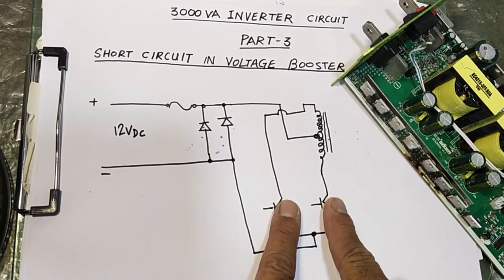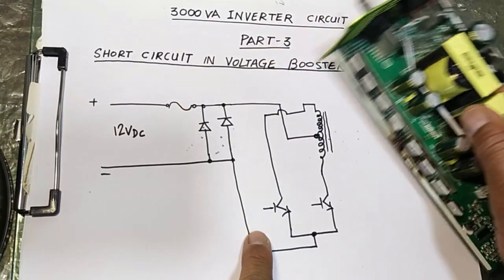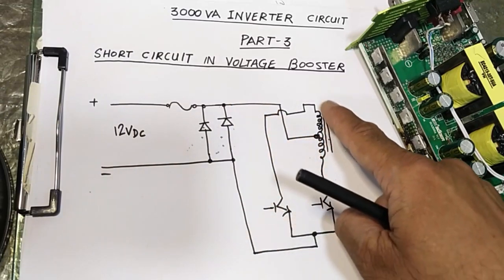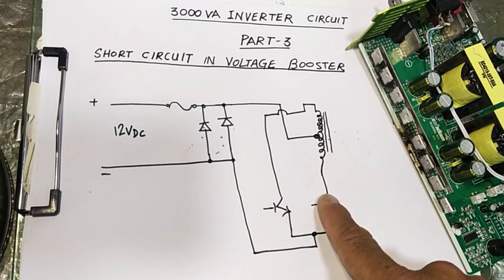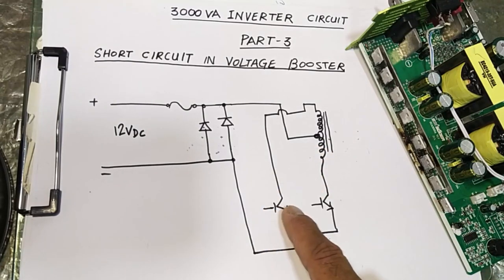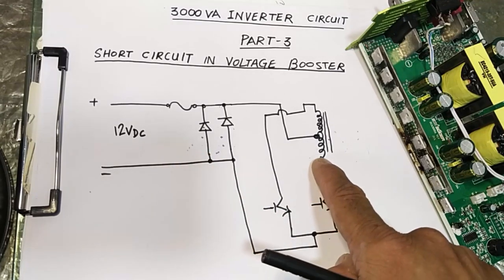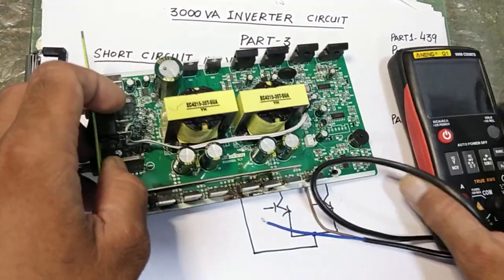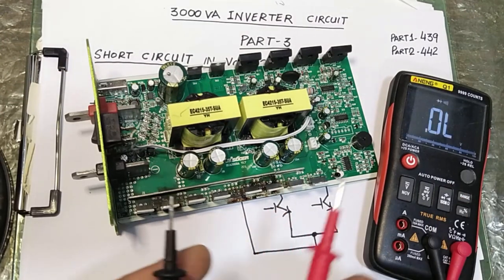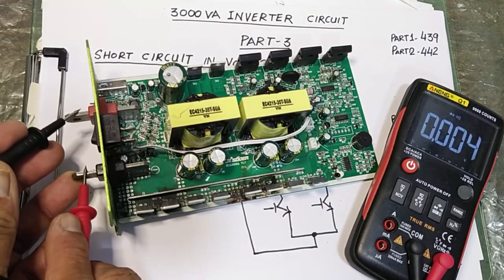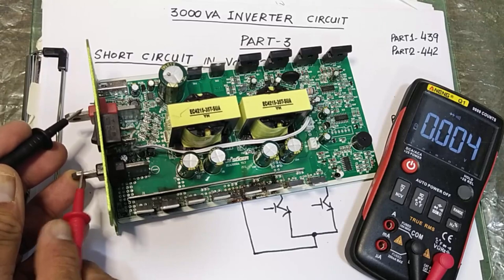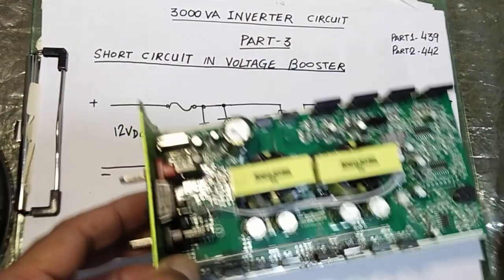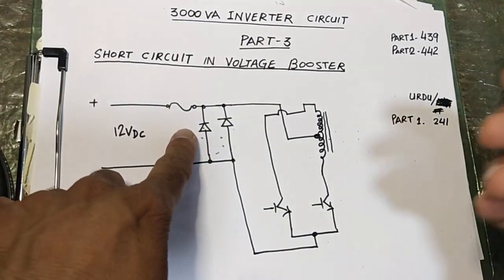In ideal configuration, positive is applied to the center tap winding of the transformer. One end is connected to one pair of MOSFET switch transistors (IGBT or whatever switching device) and the second end to another transistor. Both transistors are open in this condition, so ideally there should be no continuity. We set the multimeter to continuity or diode mode, connect to the input terminals — it reads zero, and reversing polarity gives the same resistance. That means we have a short circuit.